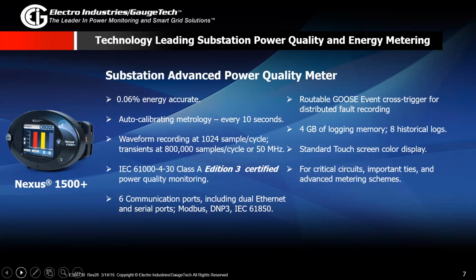This one is also certified to the IEC 61000-4-30 Class A Edition 3. This meter is actually also compatible with IEC 61850. It can do routable GOOSE event capturing for distributed fault recording. This has even more memory than the 1450. It actually has up to 4 gigabyte of logging memory and 8 historical logs. And it comes with an integrated standard touchscreen color display. So this is a really good meter for your very critical circuits, your important tie points, critical commercial where your main lines are coming in, and you really want to monitor if there are any power quality events on your main line because you don't want that to trickle down to the rest of your system.